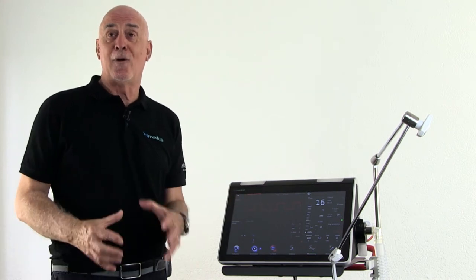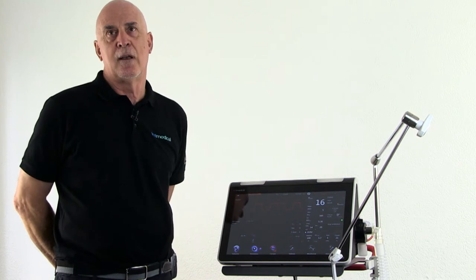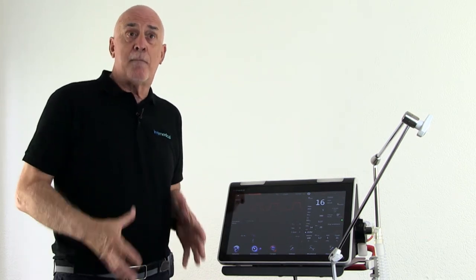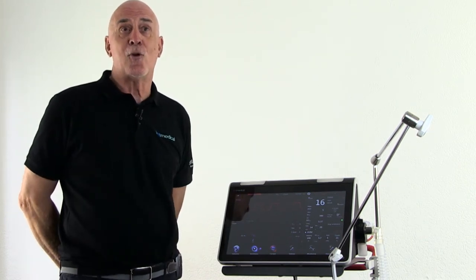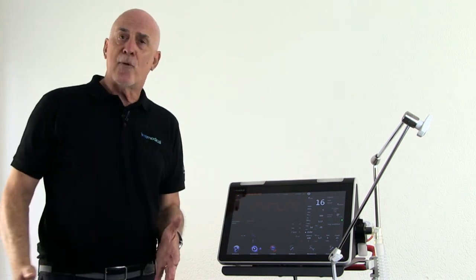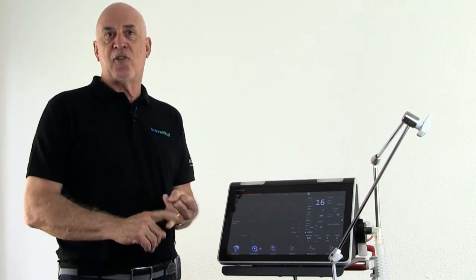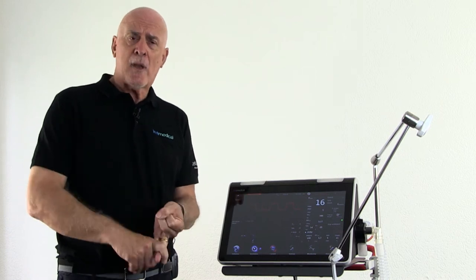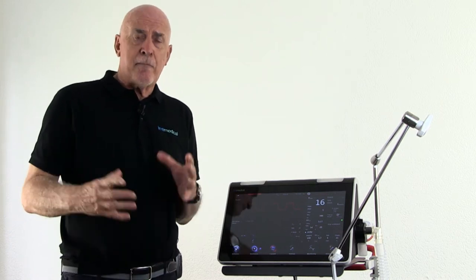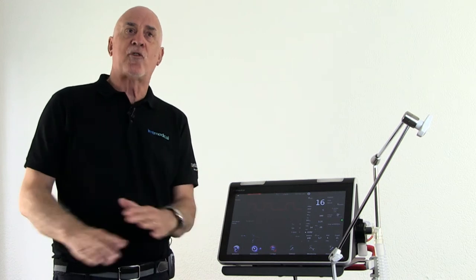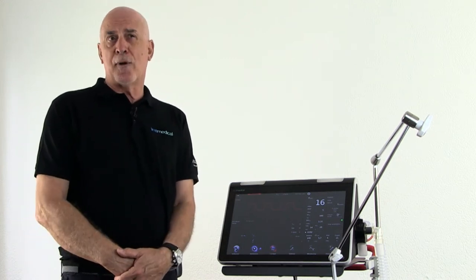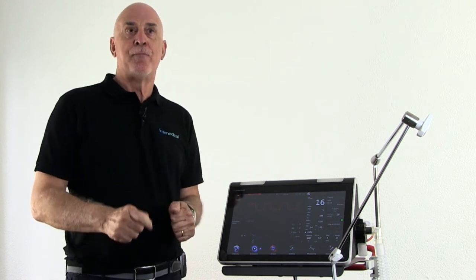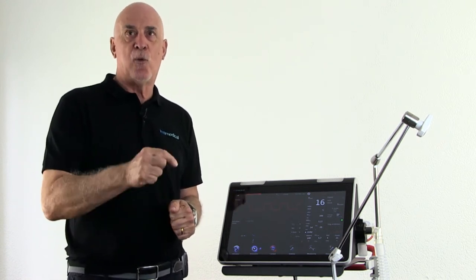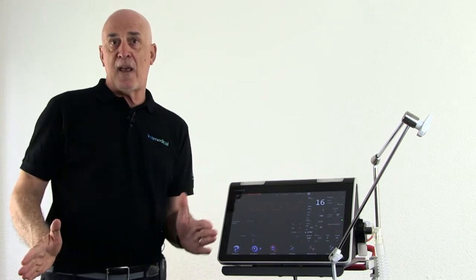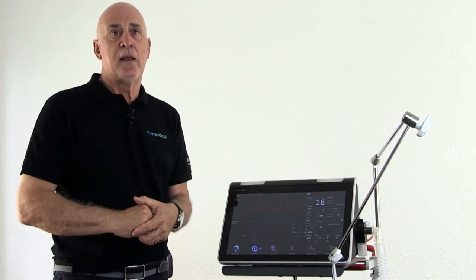So the Lung Recruitment Tool is a very unique tool, and on the Bellavista it really helps the end users do a much better job. Very, very easy. The patients need to be stabilized, number one. Number two, their blood pressure has to be good, all the risks have to be removed, and more importantly, because we have to pressurize the lung, the endotracheal tube cuff has to be overinflated to avoid leak. If we can do that, these maneuvers are quite safe.